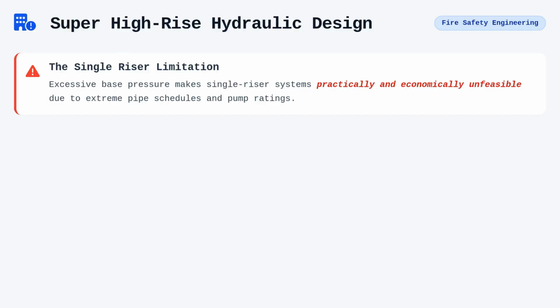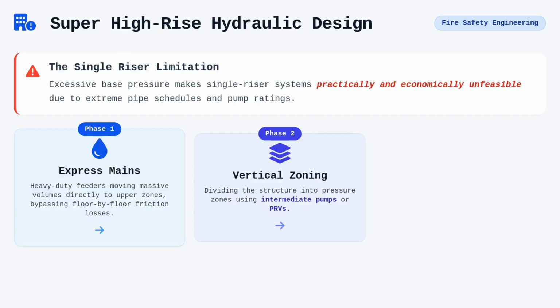Instead, we divide the building into vertical zones, using intermediate fire pumps or pressure-reducing stations to bridge the gap between these zones. Express mains act as the heavy-duty feeders that move large volumes of water from the main fire pump room directly to the upper zones, bypassing the friction losses inherent in smaller, floor-by-floor branch piping.